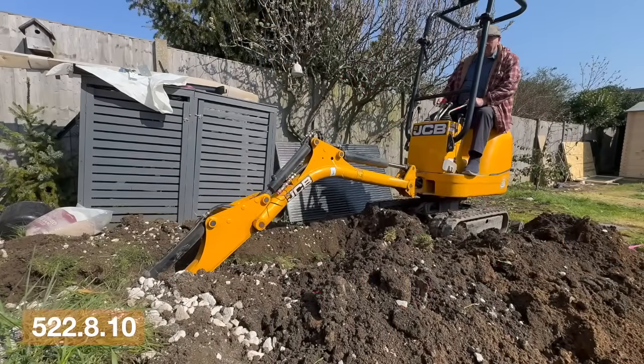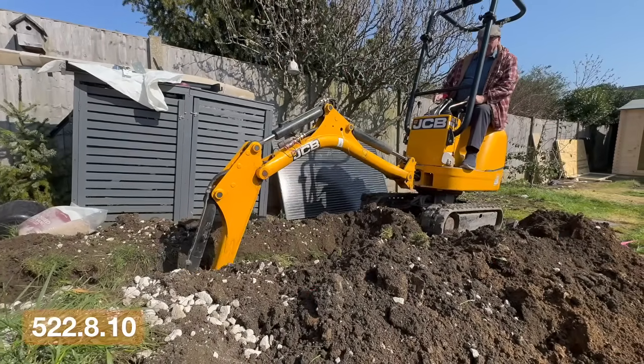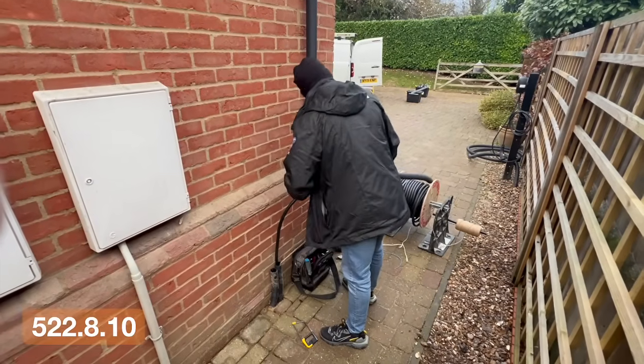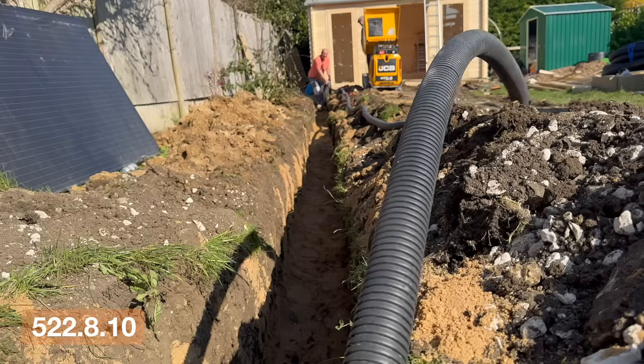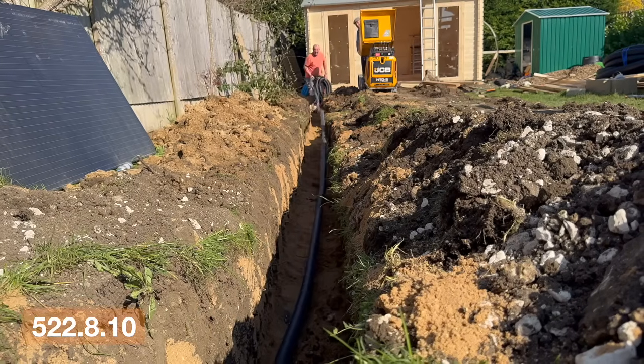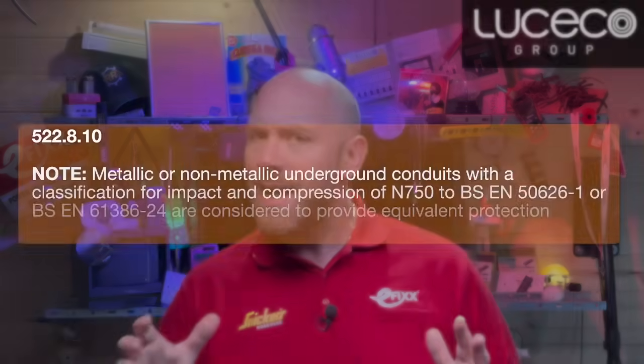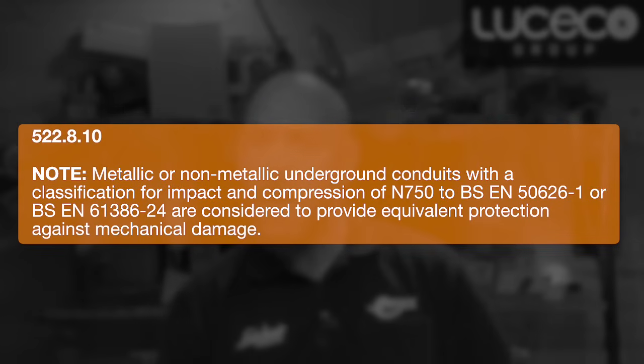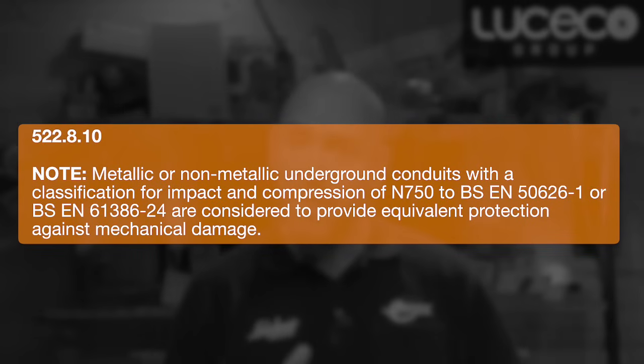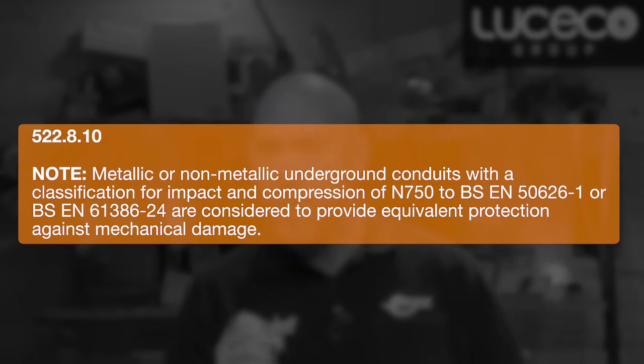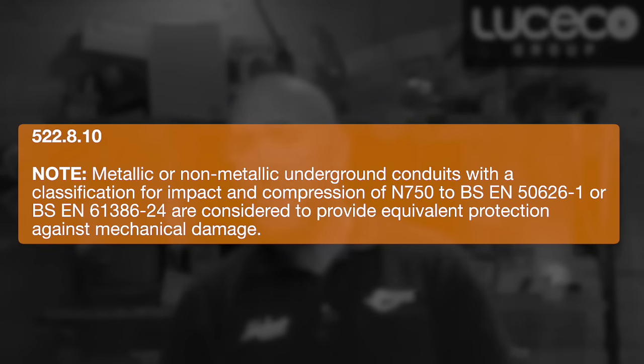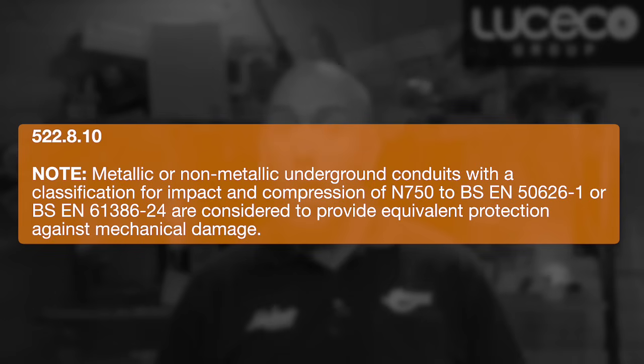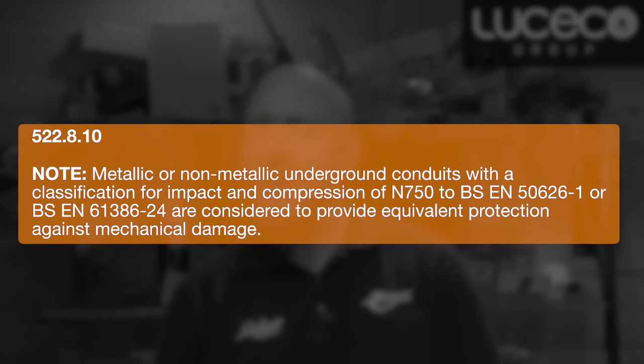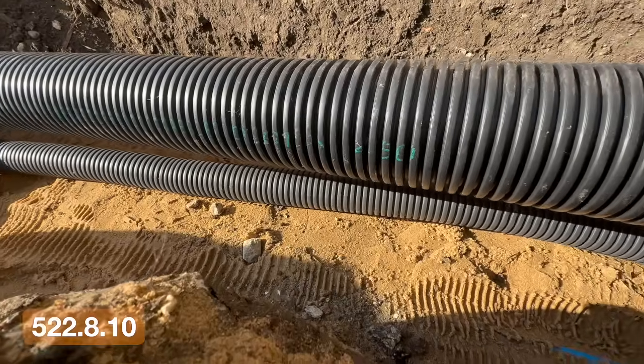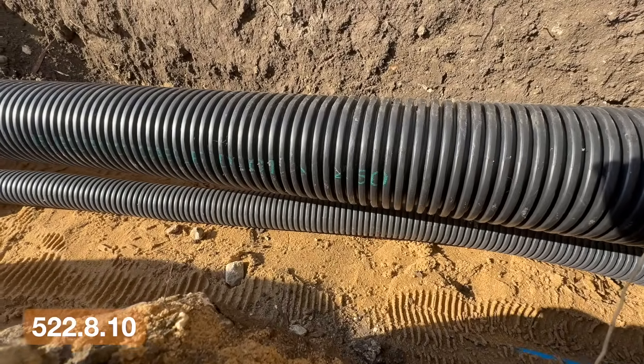Regulation 522.8.10 deals with cables buried in the ground. Here the expectation is that the cable must incorporate an earthed armour or metallic sheath, unless it is installed in a conduit or duct that provides equivalent mechanical protection. And this is where Amendment 4 adds further clarity. Metallic or non-metallic underground conduits with a classification for impact and compression of N750 to BS EN 50626-1 or BS EN 61386-24 are considered to provide equivalent protection against mechanical damage. So if you're using ducting as your method of protection, it now needs to meet the N750 classification.